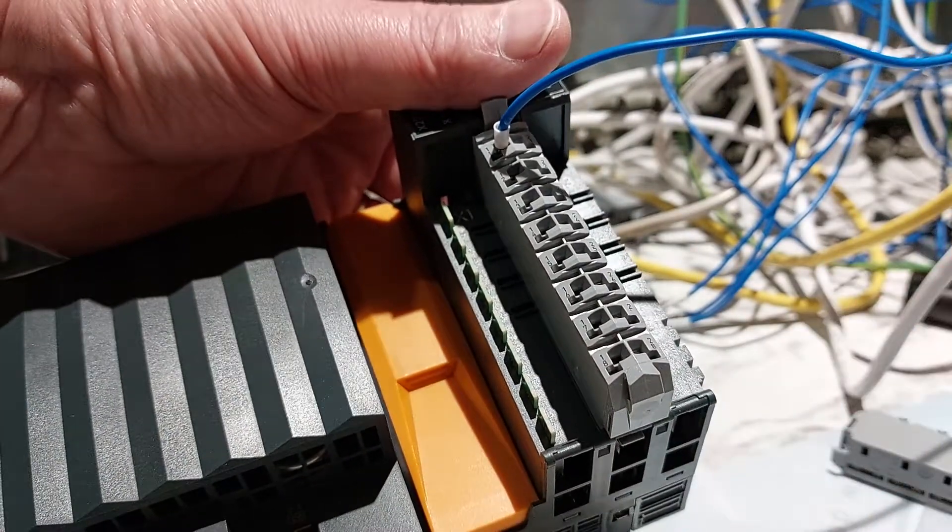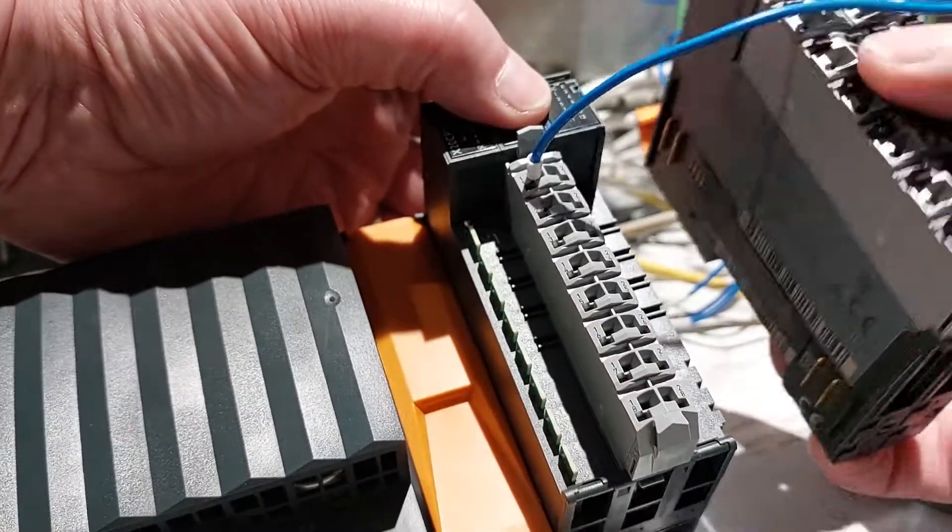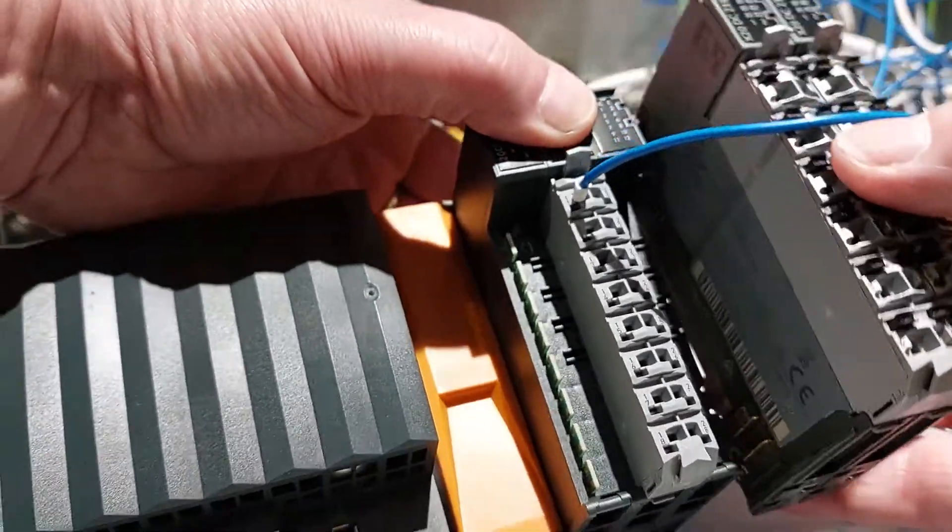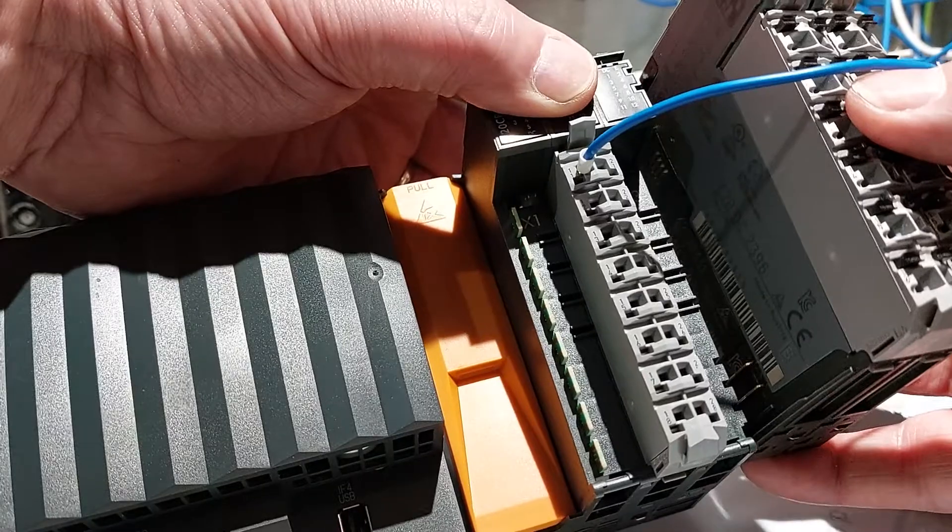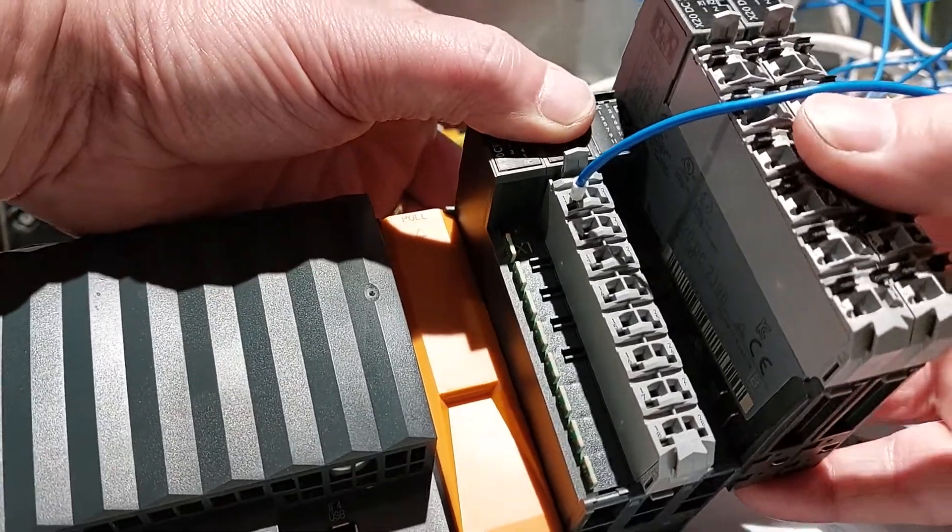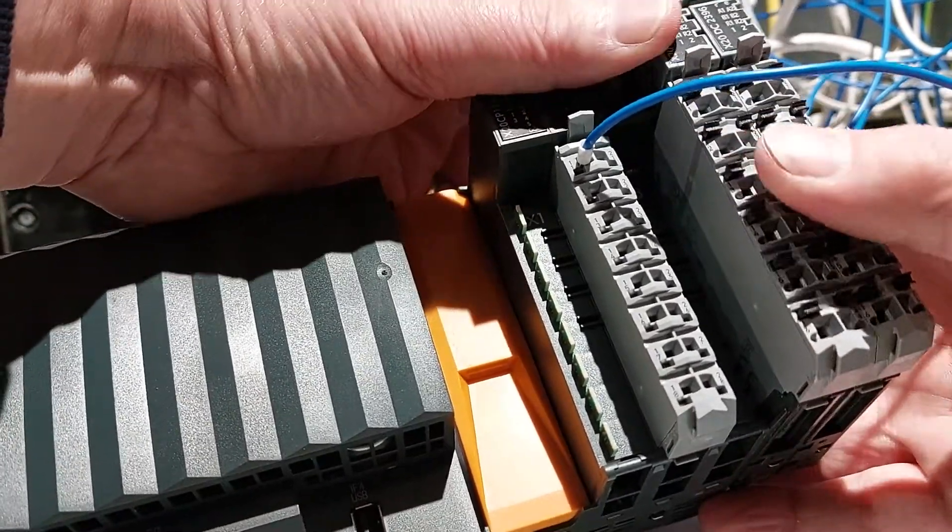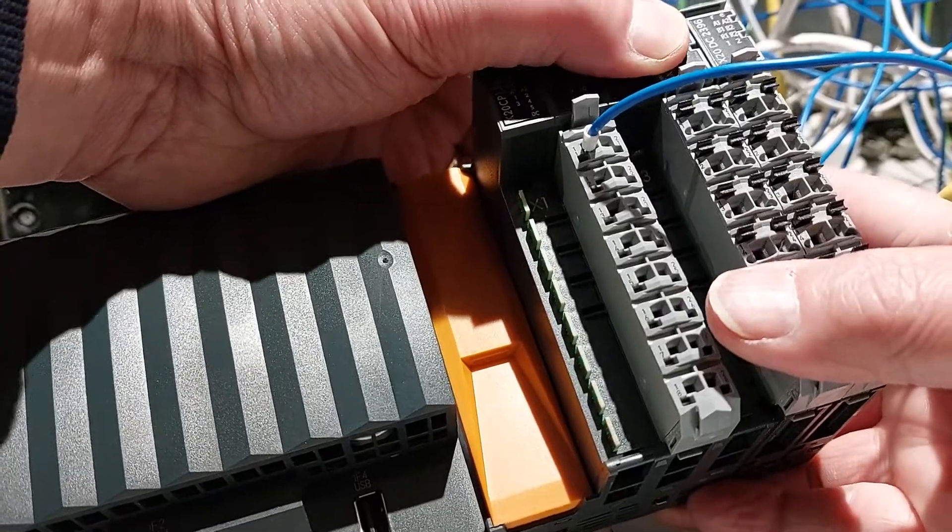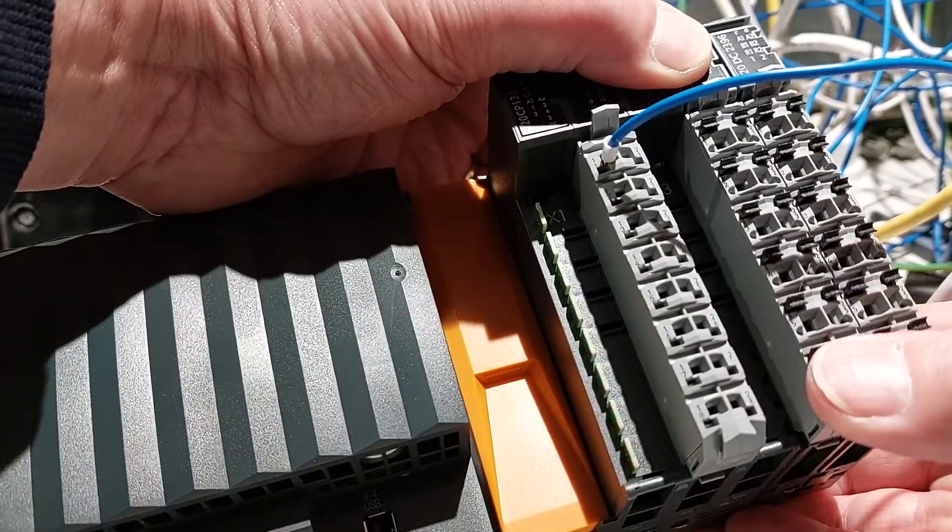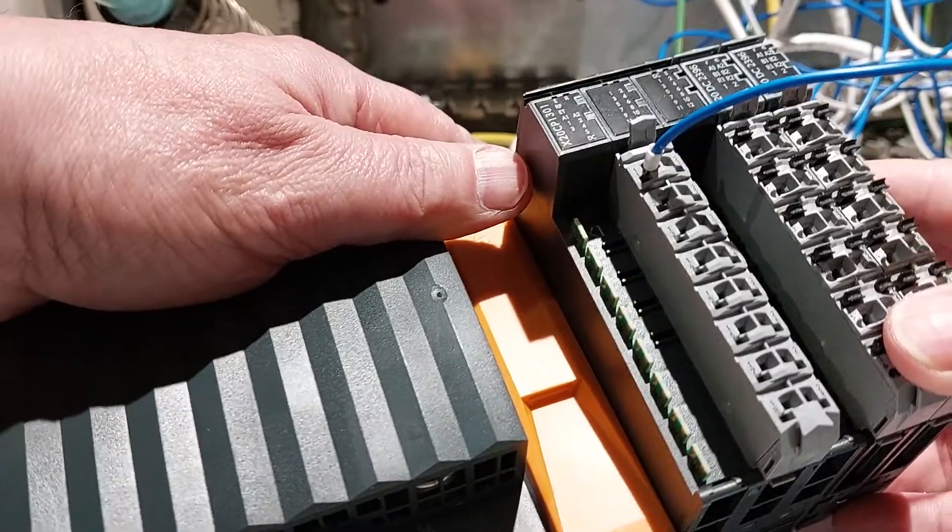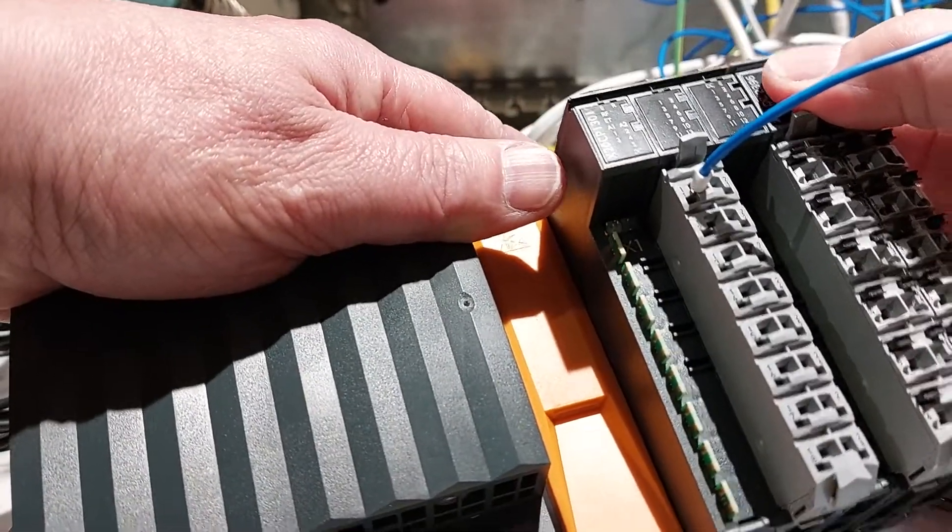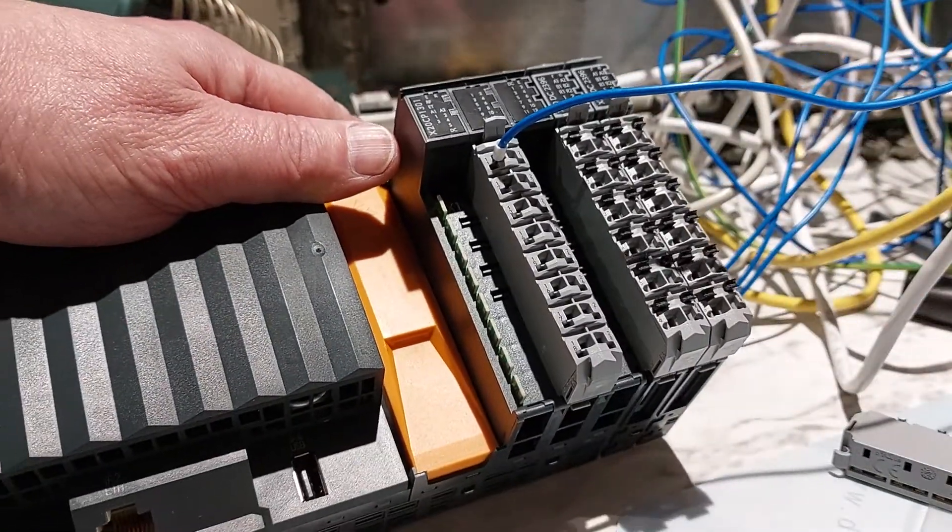So in order to put it in, take the terminal block off, locate this. There are some guides there at the top and the bottom. Slide it on, back in, and that should be retained. If you move it here it doesn't move, move it here it doesn't move. So that is your module removed and replaced.